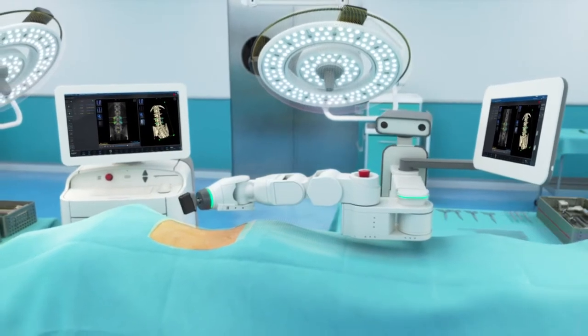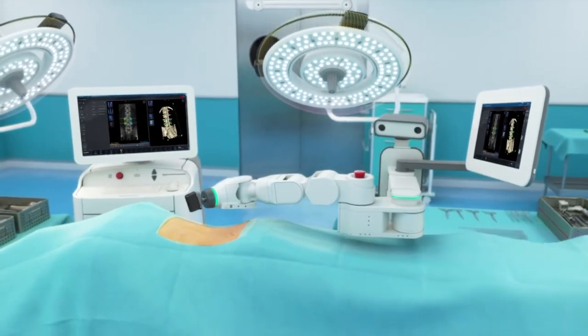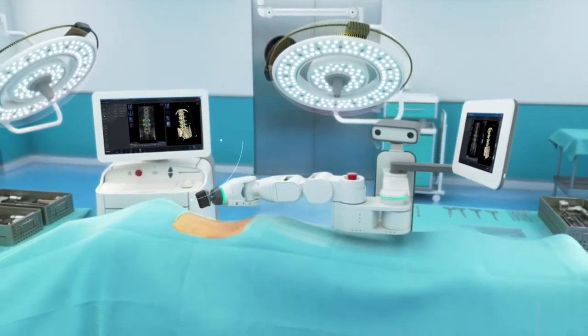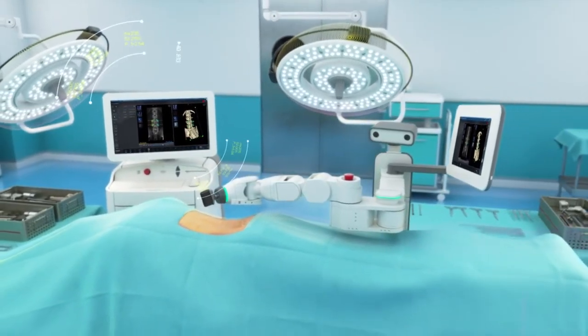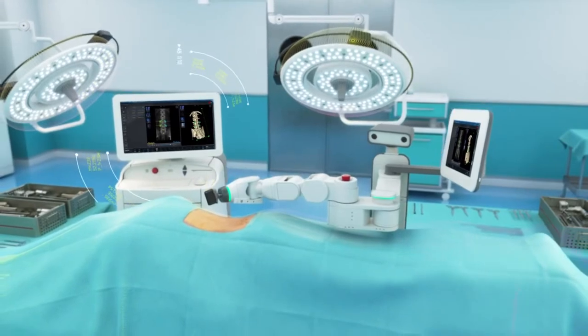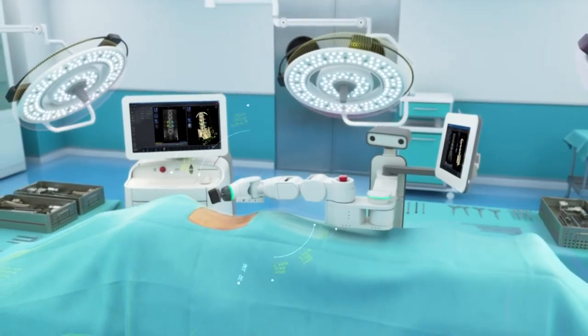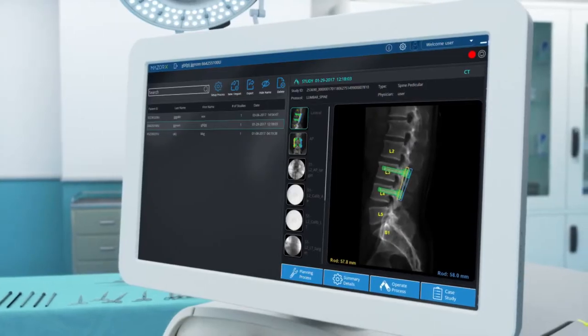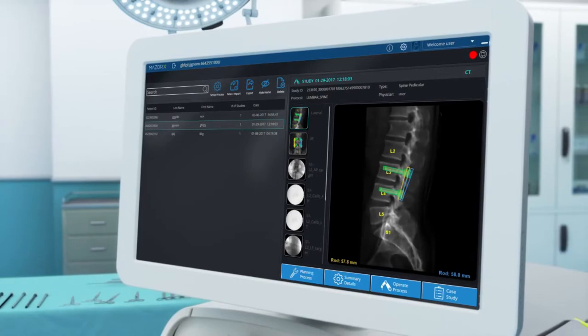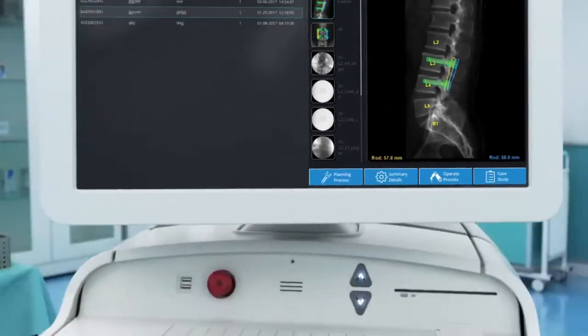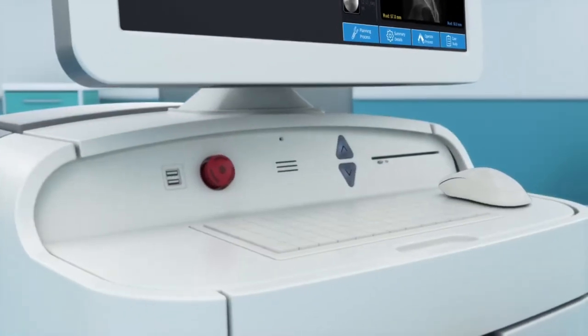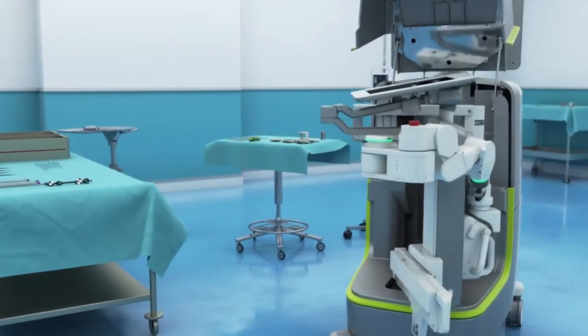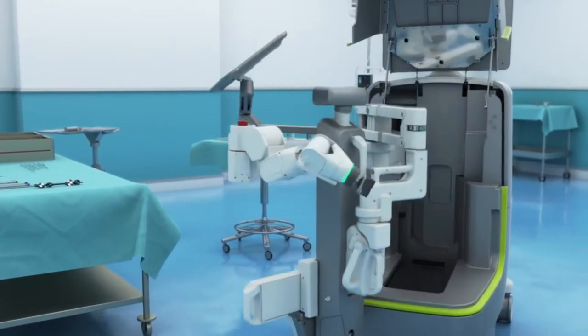Mazor X consists of sophisticated software and algorithms running on a workstation and a precision guidance system with a surgical arm. The workstation includes a large touch screen serving as a surgeon control panel, hardware components and storage for the guidance system.